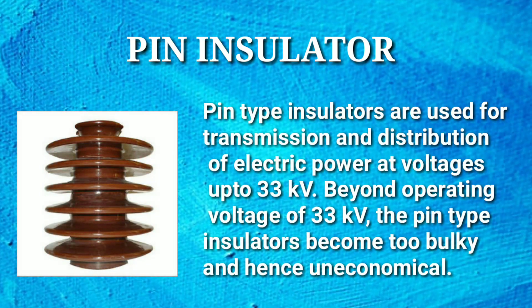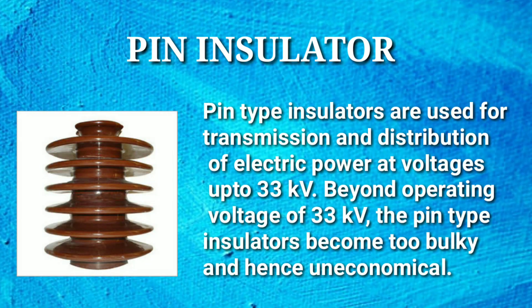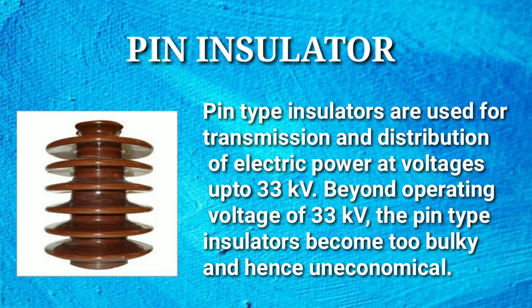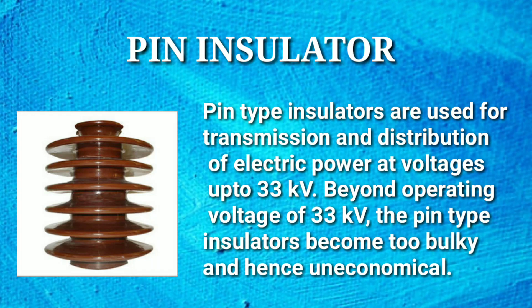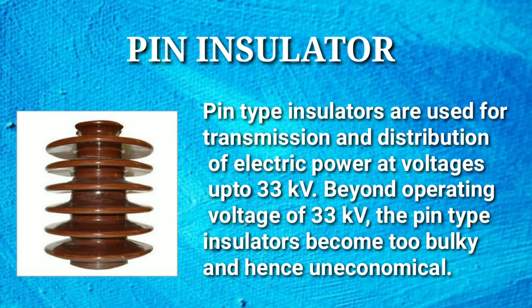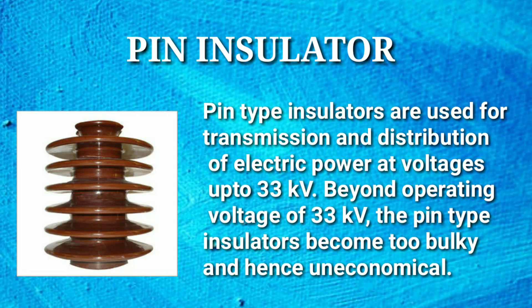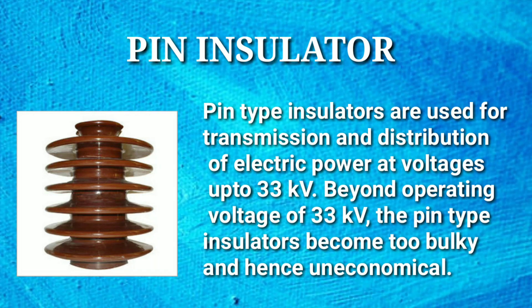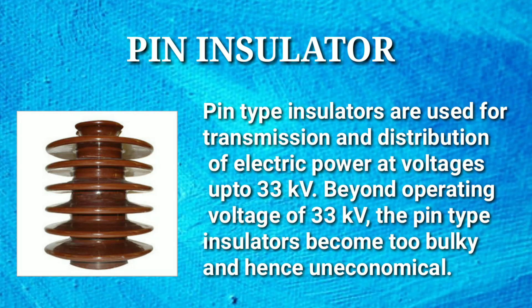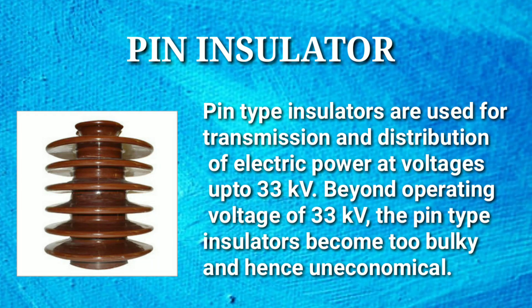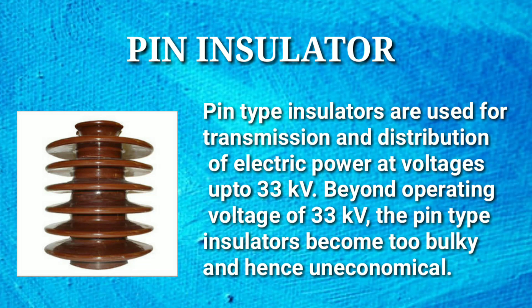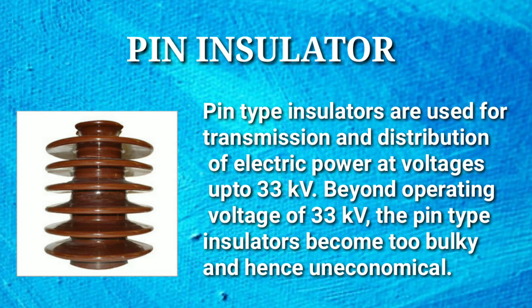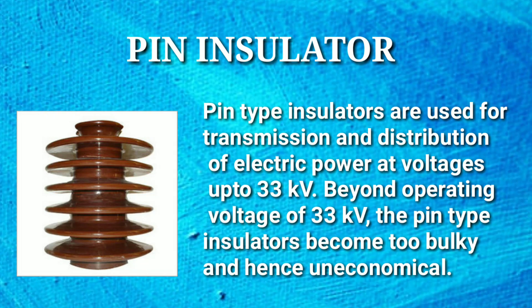Pin type insulators are used for transmission and distribution of electric power at voltages up to 33 kilovolts. Beyond operating voltage of 33 kilovolts, the pin type insulators become too bulky and hence uneconomical.